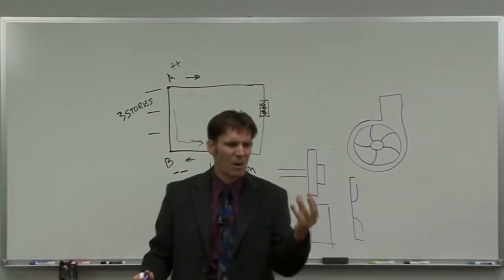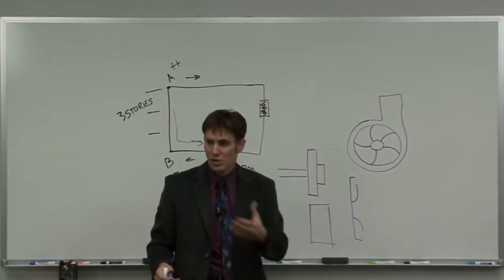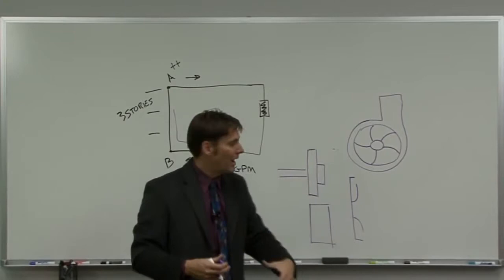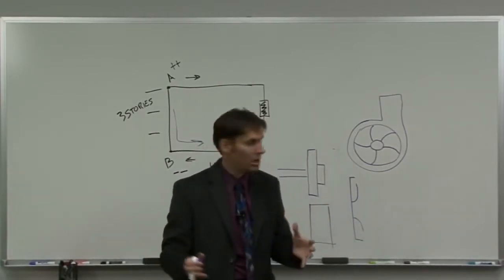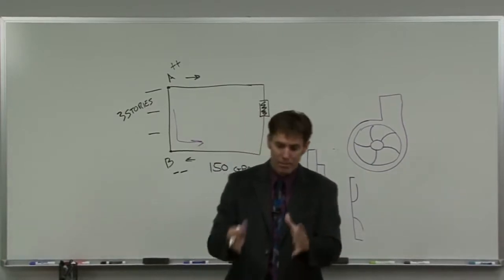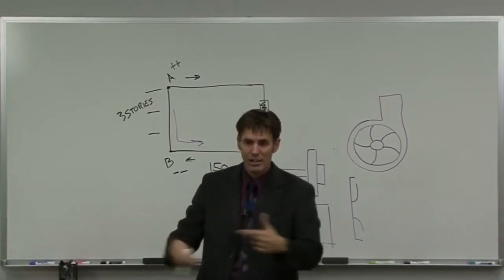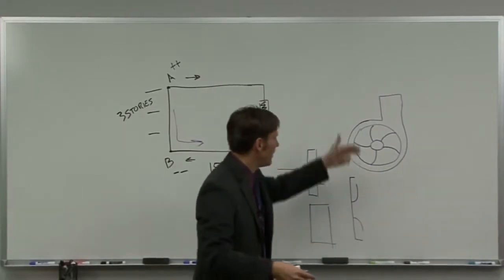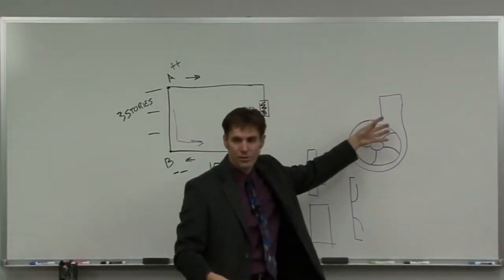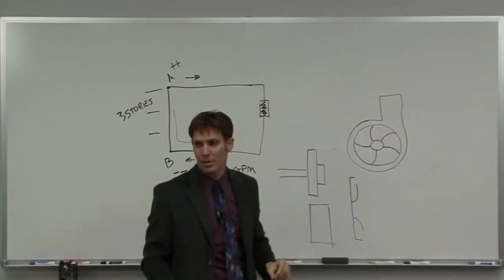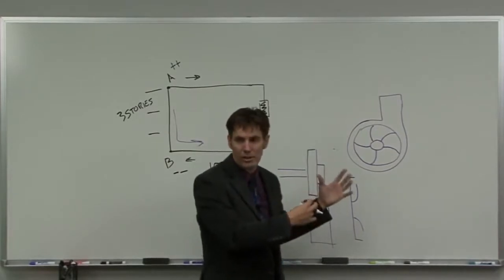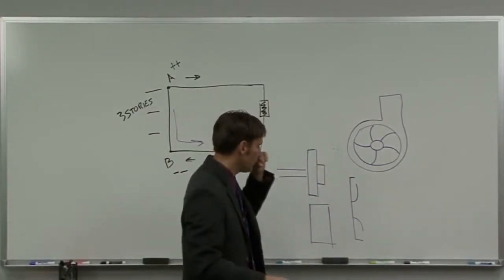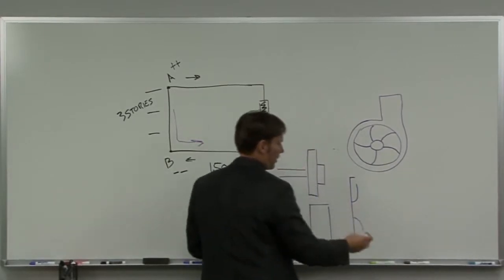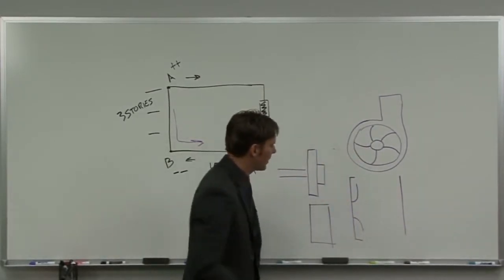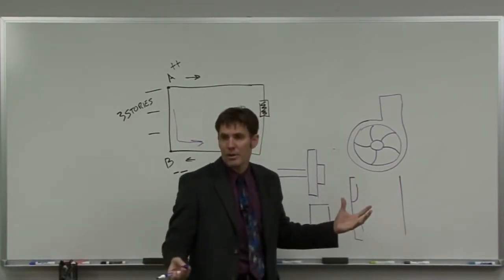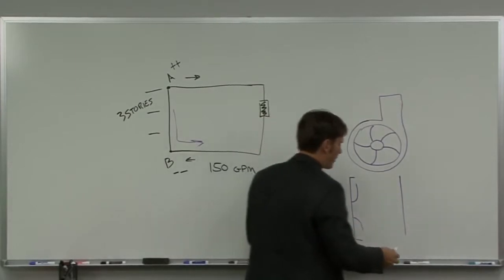There's really three parts to most pumps. You've got the drive assembly, which is the motor, and the motor shaft. If you get into a split coupled type pump or a flexible coupled pump, you're going to have a bearing assembly with the pump shaft. Again, it's still part of that drive assembly, but it's there to drive the impeller, to rotate the impeller inside of the volute. It's these two components that make up the pump curve. Everything else is there to support it, to drive it, and to create that pressure. If we have an open face impeller, you're going to have more. We see this in plumbing applications so that we can pass a 2-inch solid if we're using a pump in an effluent type system or some heavy wastewater type system.